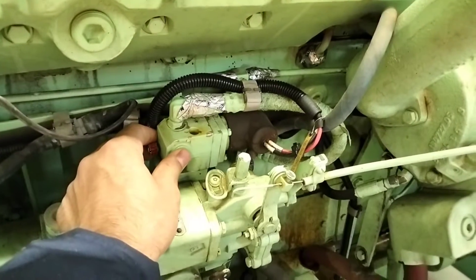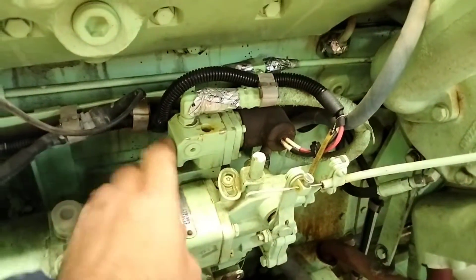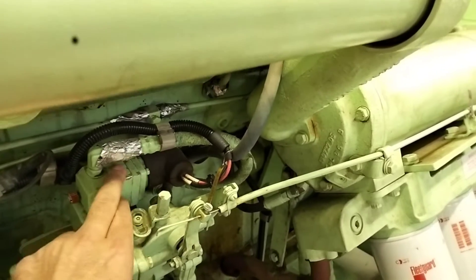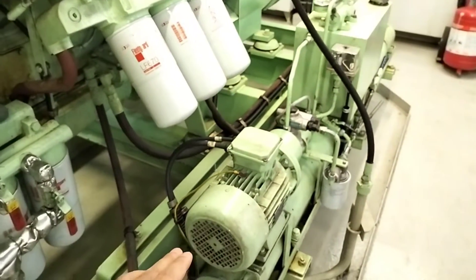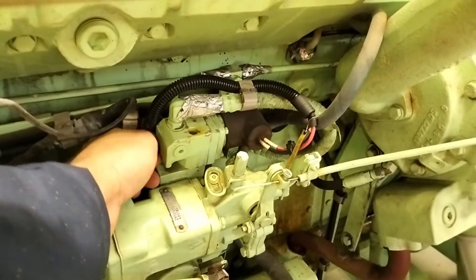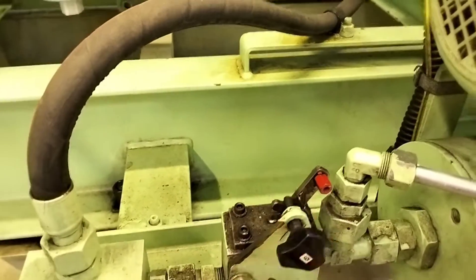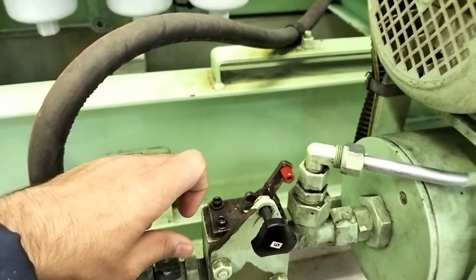You have to come here. This is the fuel solenoid valve, so we have to press this knob inside to activate this fuel solenoid valve. What is the purpose of doing this? Because when we start this emergency generator with the help of the battery, there is an electrical signal coming to this solenoid valve to activate it. But now we have no battery power and we are going to start this generator with the hydraulic system. For that reason, we need to activate this solenoid valve manually by inserting this knob inside, so that we can open this fuel valve. After that, you need to remove this cover, and then pull this red lever all the way down until the generator starts completely, then you can release.